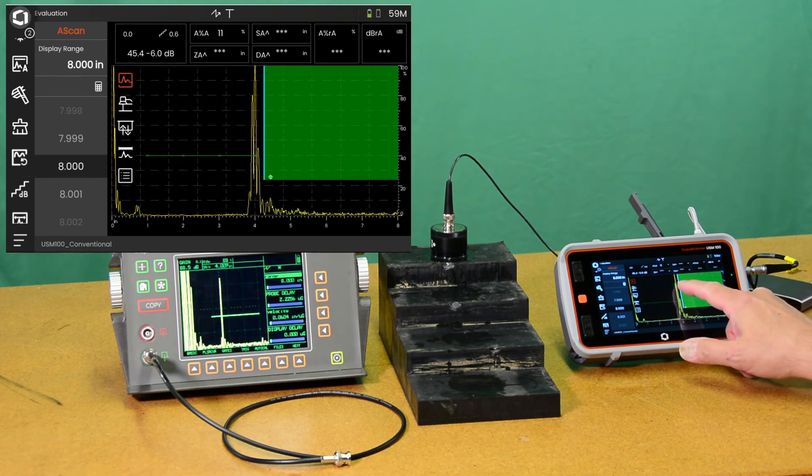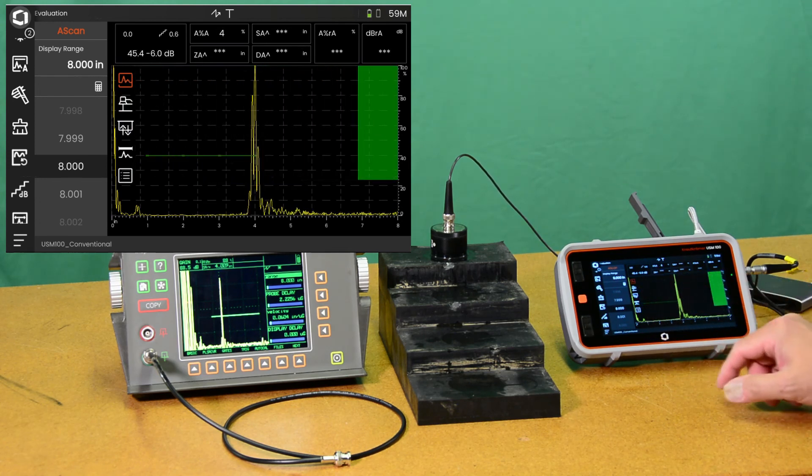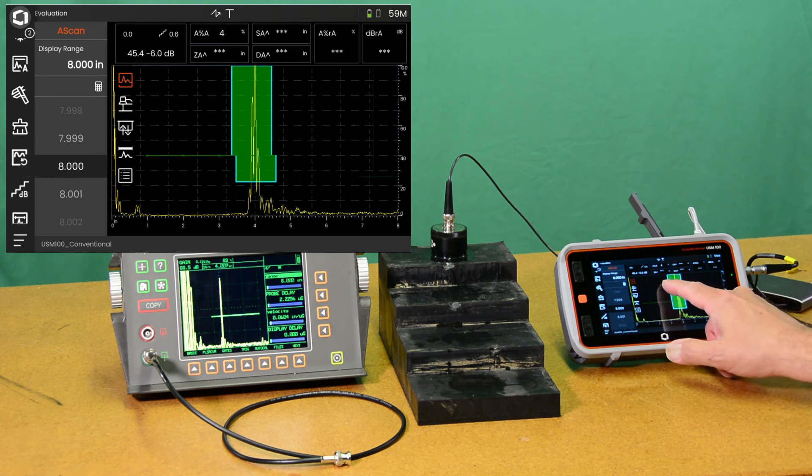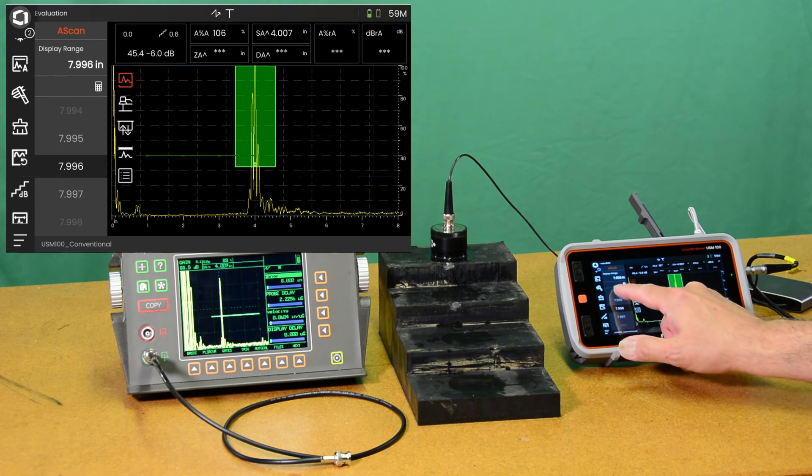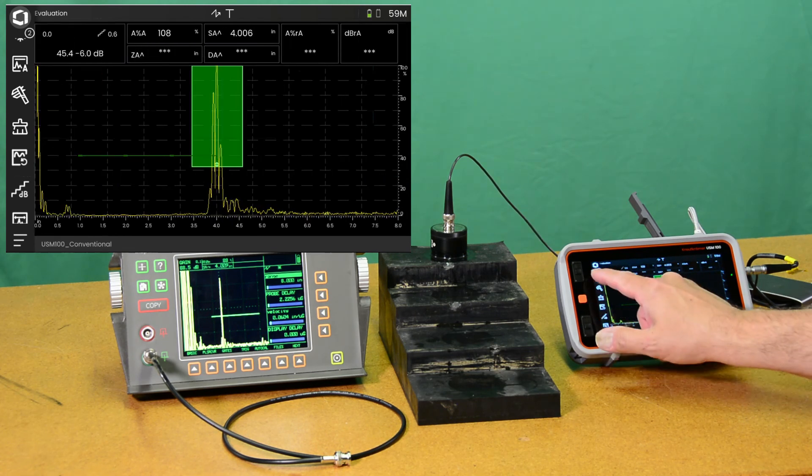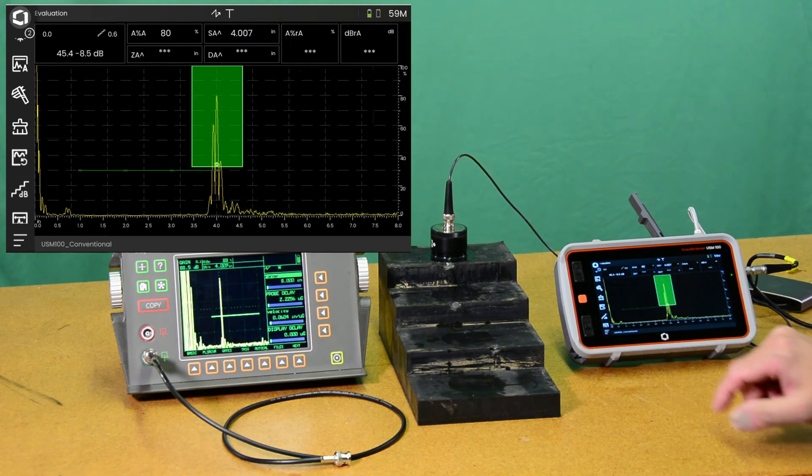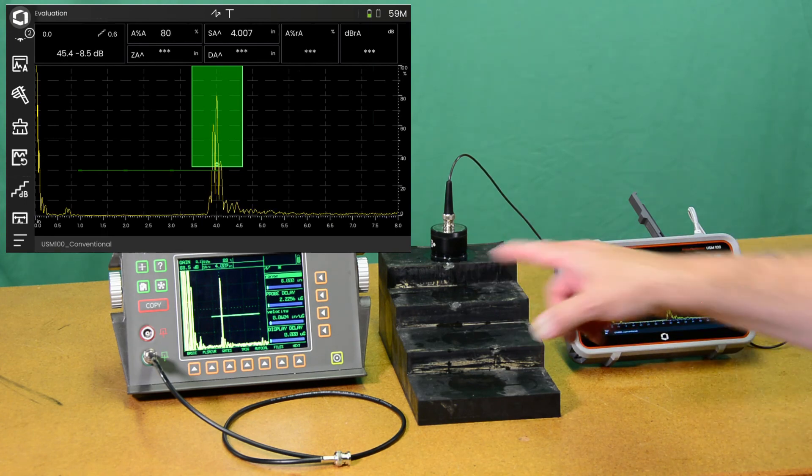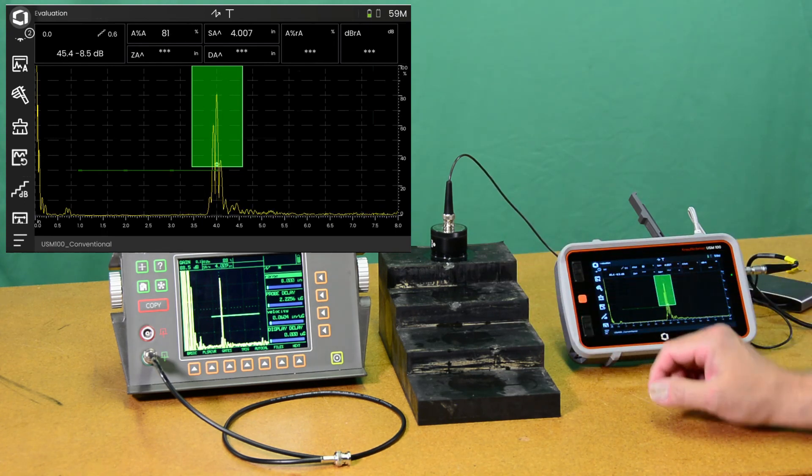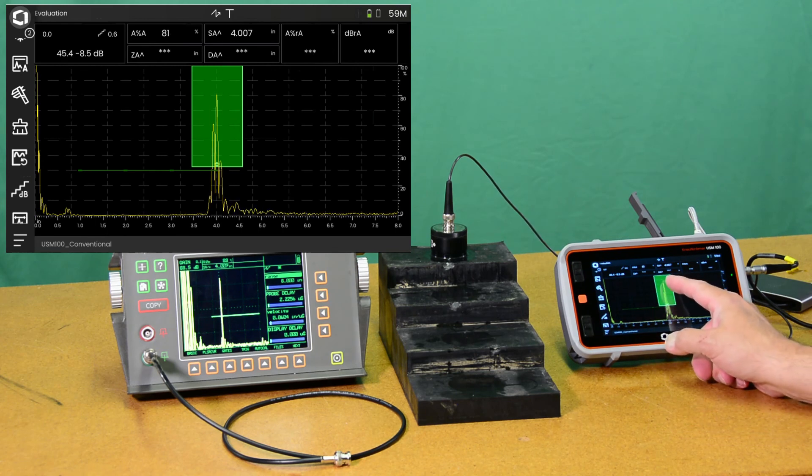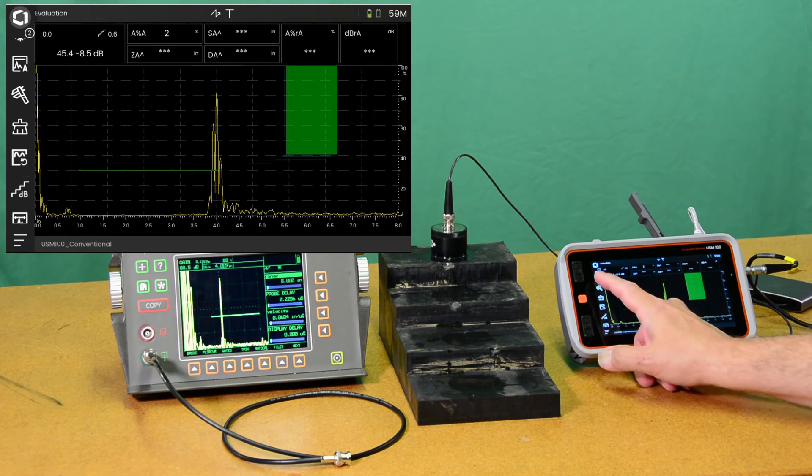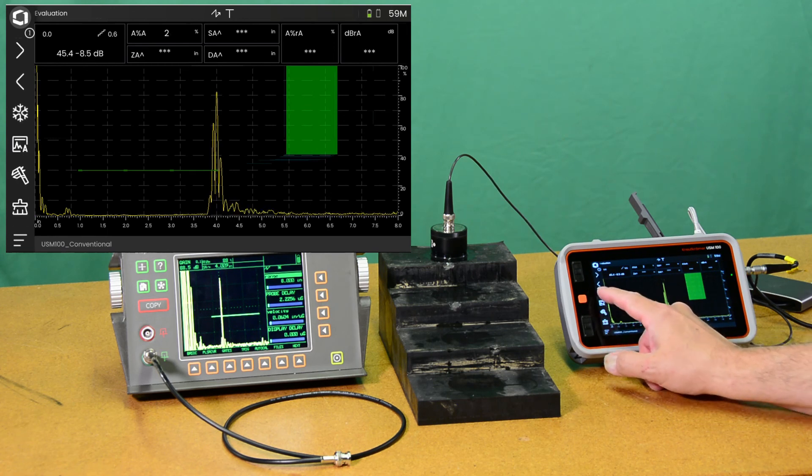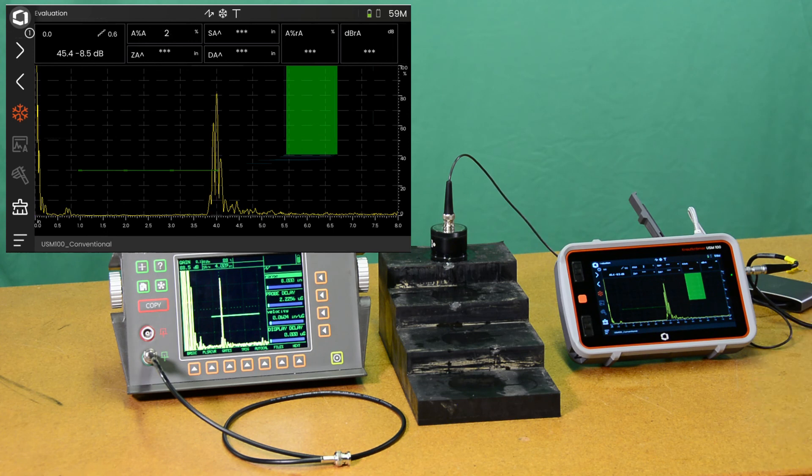There we have sort of an apples to apples comparison. Move our gate out of the way here so that you can see the echo nicely. Hide the menu. Do an auto 80. Now we have apples to apples. Eight inches of range, just like on the 60. We have our echo at 80%. We're running live. I can scroll down here, hit the freeze button, and freeze that. So there's a good side-by-side comparison.